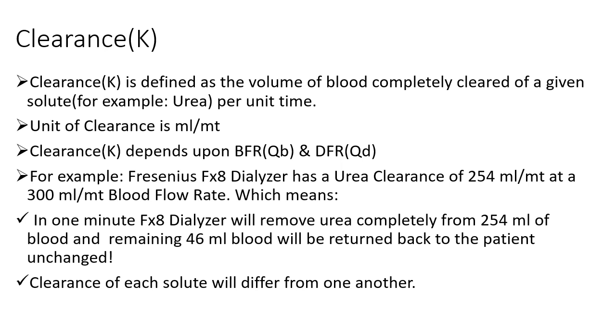For example, imagine we have an FX8 dialyzer with a urea clearance of 254 ml per minute at a blood flow rate of 300 ml per minute, as per the brochure. This means the dialyzer can remove all urea from 254 ml of blood, but the remaining 46 ml will not be cleared of any urea, because our dialyzer's urea clearance is only 254 ml per minute while blood flow rate is 300 ml per minute.